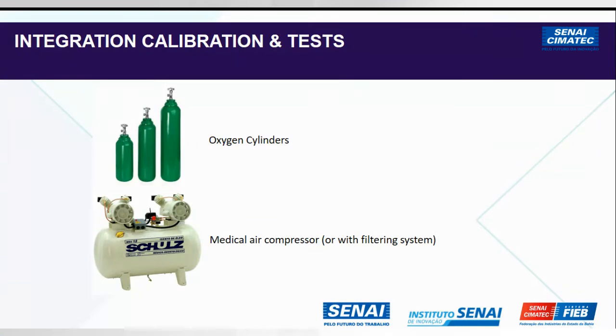When I say the equipment is cycled the same way as the patients, you need to use oxygen cylinders and medical air compression. The medical air compressor is very important. It must be free of oil and water. You have the dry system, the filter and dry system, to guarantee that no water is pushed inside the ventilator.